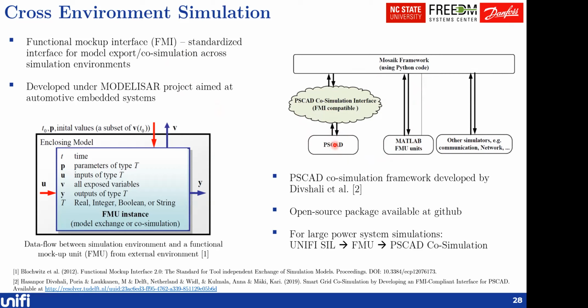So ideally, what we could do here is that the SIL models that we showed in the earlier slides, we take that control software and we also take the power stage and convert that to a set of ODEs. So basically, the whole IBR becomes an FMU, and we export that to basically do co-simulation with PSCAD. That is an idea that we can explore probably in the UNIFI ModSim group.